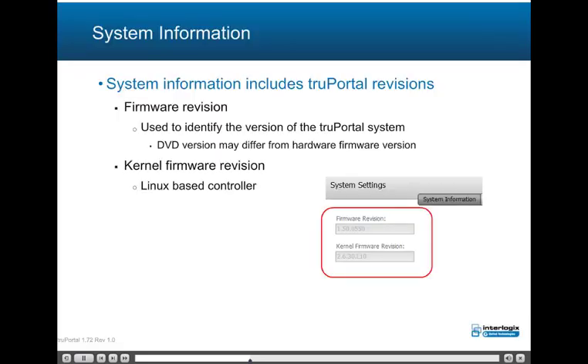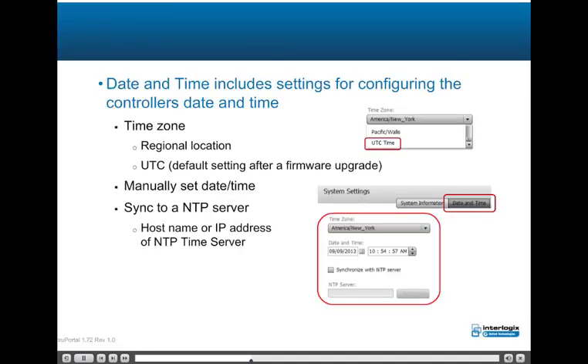System information includes the TruPortal firmware revision, used to identify the version of the TruPortal system; note the DVD version may differ from hardware firmware version. Also shown is the Linux kernel firmware revision. Date and time settings configure the controller's date and time, including selecting the time zone — note UTC is the default setting after a firmware upgrade. The date/time may be set manually, or the system controller may be synchronized to an NTP server by either host name or IP address.